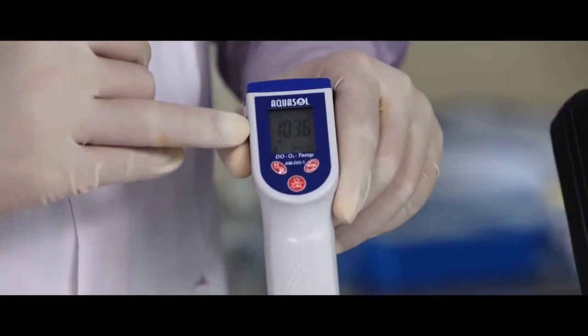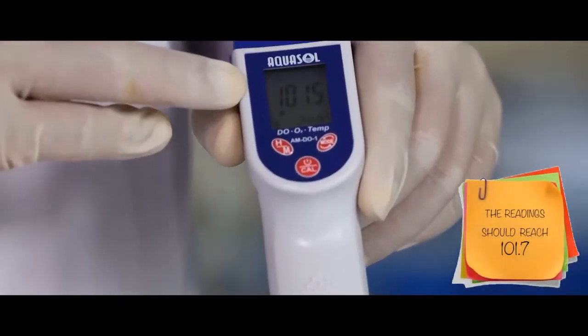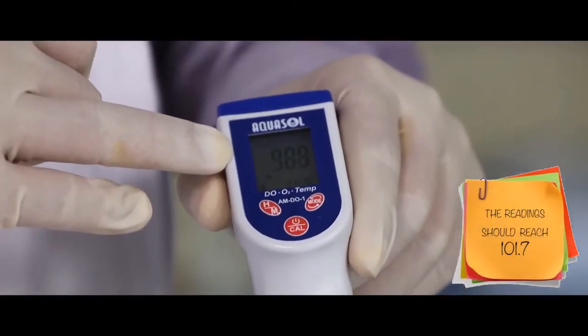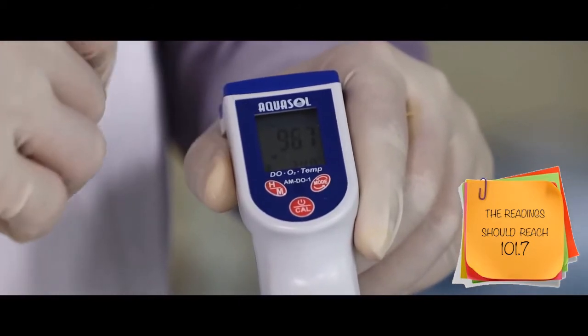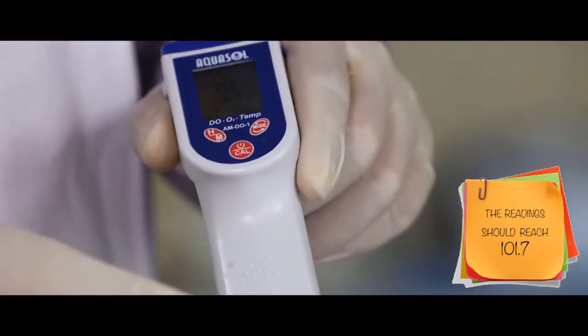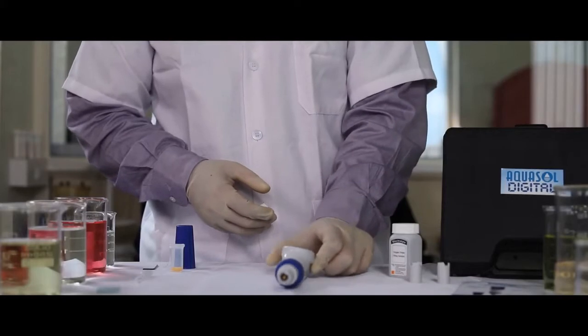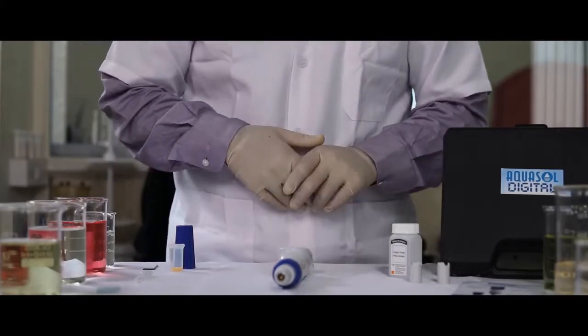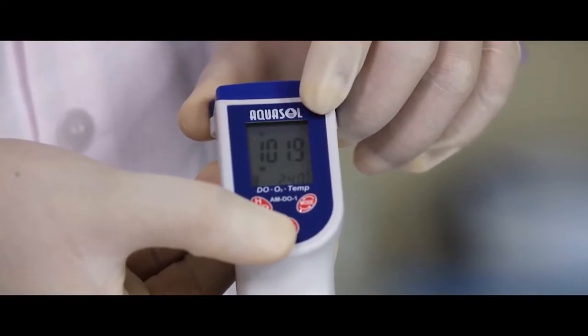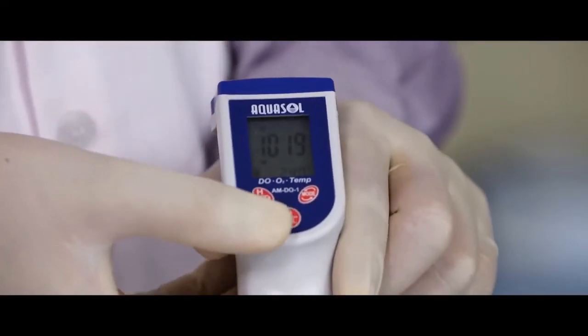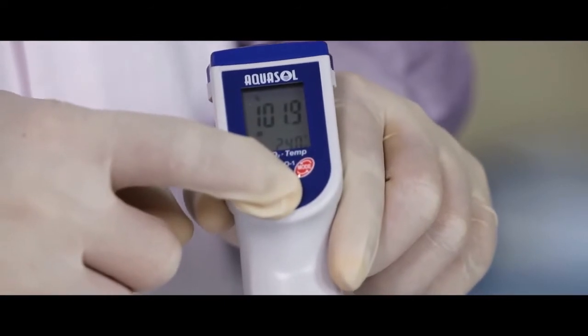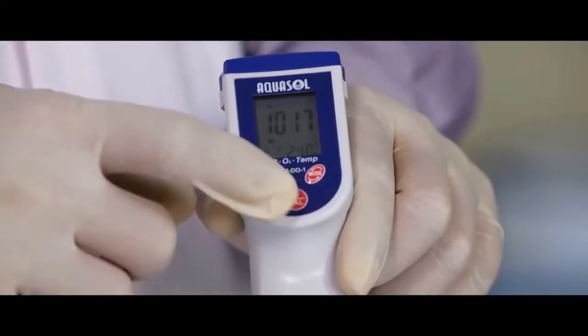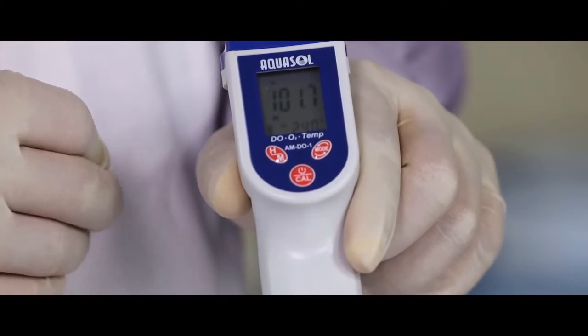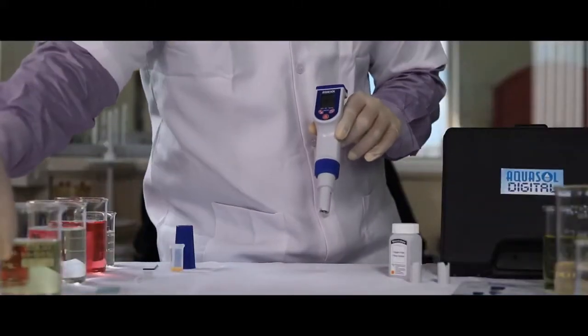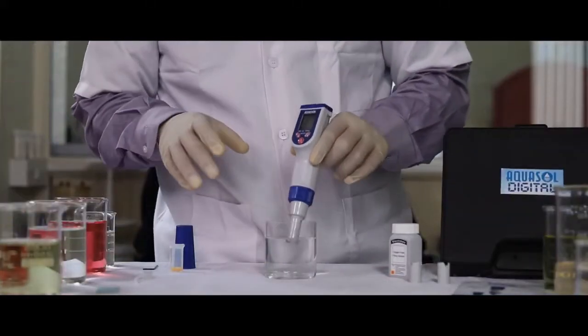Now turn on the meter. The meter will take about 20 to 30 minutes to polarize. The reading should reach 101.7. Once the meter reaches a stable value, press the Cal key on the meter and the meter will calibrate it to 101.7. Calibration done. Take the sample to be checked and dip the meter in the sample.